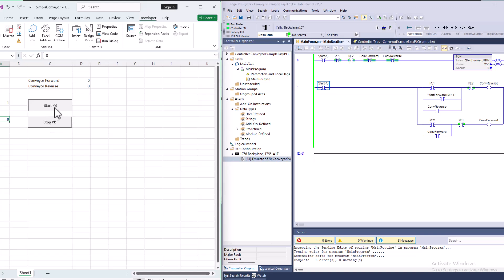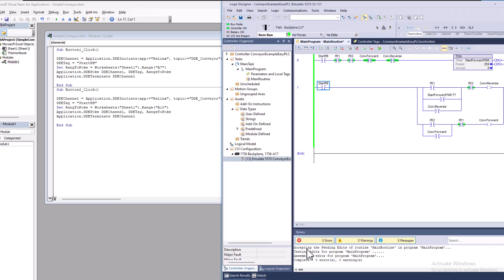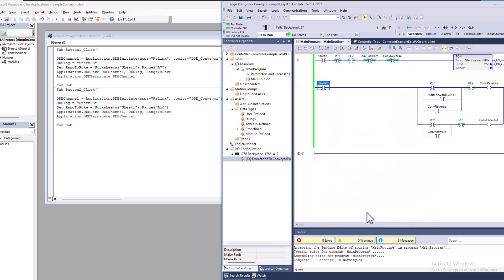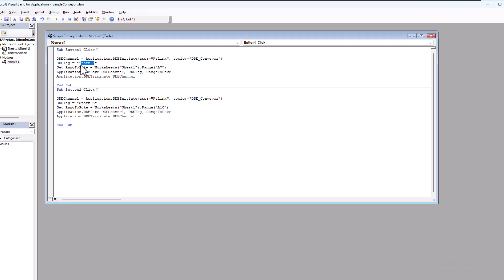So what we need to do is troubleshoot why we don't have a working system. And we can troubleshoot and see why we're not using the tag that we have used. Start push button. And sometimes it's a matter of coming in here and looking at the start push button. Is it just being used or what kind of tag is it? Is it a controller tag? It needs to be a controller tag to be able to use it. So that is the start PB. We can double check that by just coming over here, copying this. Come over here and pasting it in here just to make sure we have everything correct.